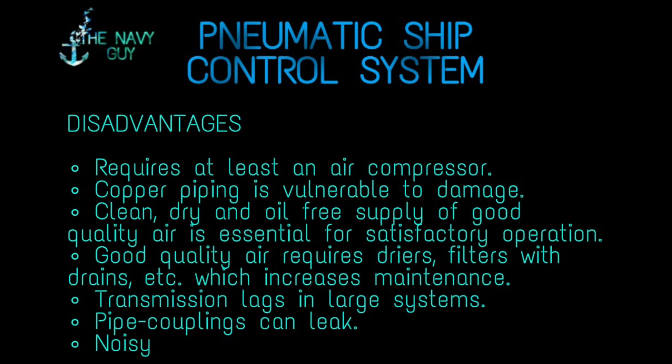Some disadvantages of the pneumatic ship control system are: it requires at least an air compressor and associated air systems; the copper piping is vulnerable to damage very easily; a clean, dry, and oil-free supply of good quality air is essential for satisfactory operation; good quality air requires dryers, filters with drains, etc., which increases maintenance; it may have transmission lags in large systems; pipe couplings can give rise to leaks in certain ambient conditions; and it has some potential noise.